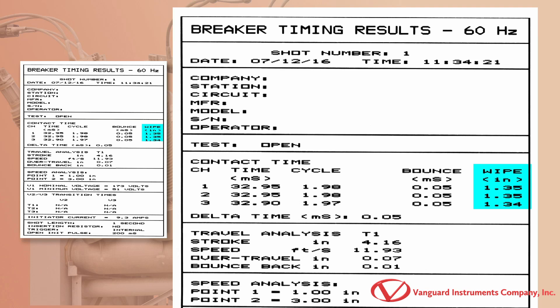The contact wipe distance is measured and printed under the wipe column. The wipe measurement is shown in millimeters or inches depending on the user's preference. The delta time is shown here. This is the difference between the fastest and slowest contact time.